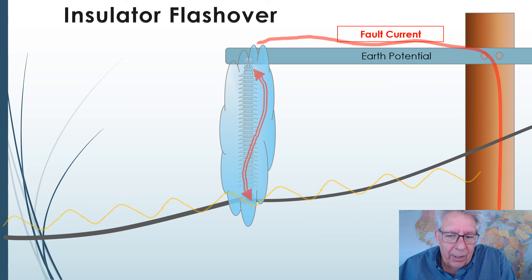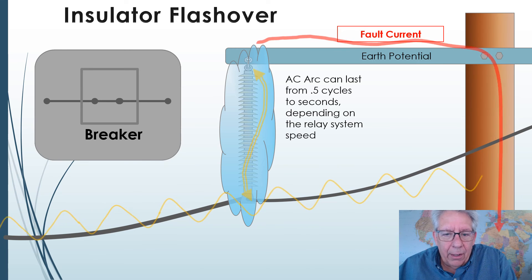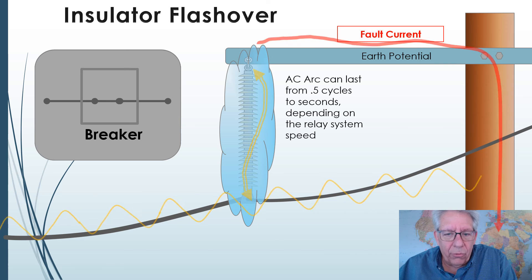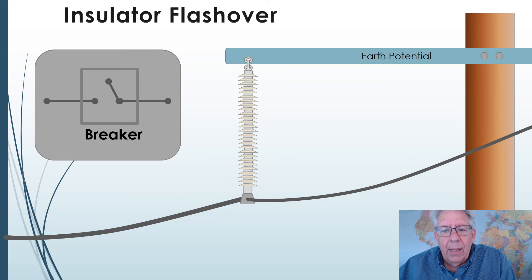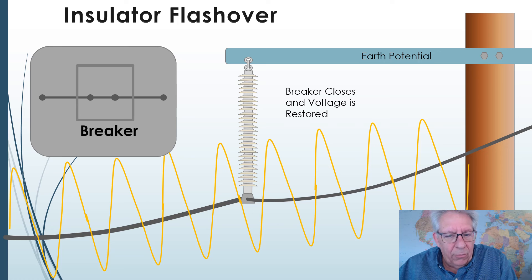Well, it stays like this until the breaker is activated. So when the breaker opens finally, the AC breaker from the source, the current stops flowing and the arc disappears. And then the recloser or the breaker closes and AC voltage is restored back onto the line.